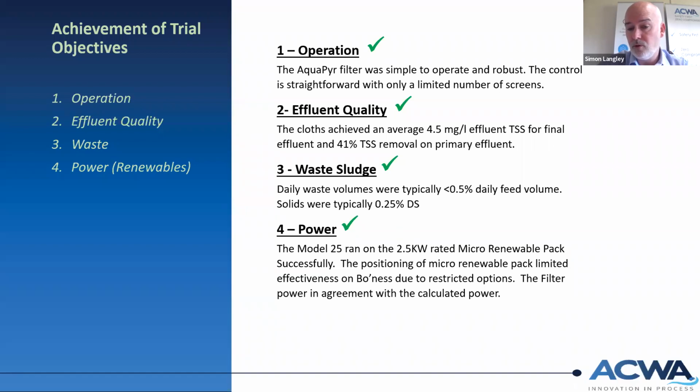Both of these were great results, but the final effluent result is really encouraging because when combined with either algal treatment, electrocoagulation or traditional dosing, we know that the unit will now achieve 0.5 mg/L of phosphorus or less, which is great because it opens up that phosphorus removal challenge, which is current for everyone.